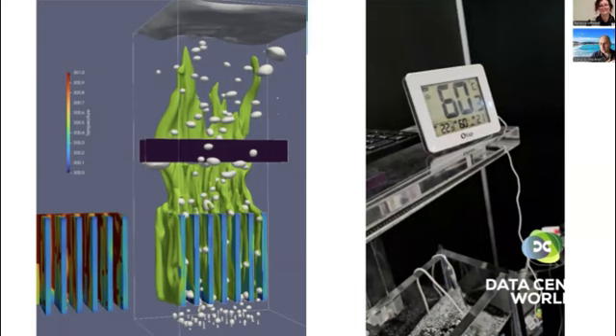There does exist two-phase immersion, but two-phase immersion has different issues with the impact on the environment, with the carbon footprint of those fluids, etc. But single phase immersion has a limit of 500 watts. So what they have done, they created conditions like two-phase immersion by injecting bubbles into the hotspots where we have these GPUs or CPUs. And by this, they achieve a much higher thermal design power of the CPUs and GPUs and much higher temperature of the fluid. So I want to show just a quick video which shows that there is 60 degrees immersion fluid and how it works.